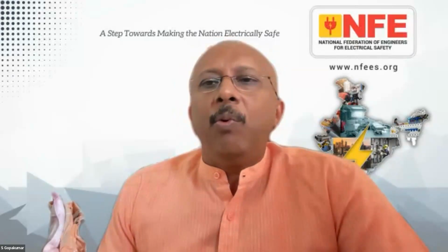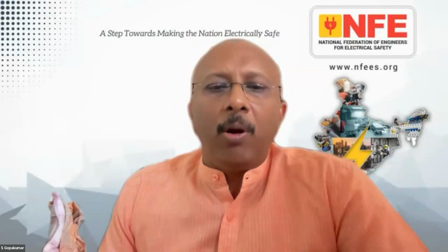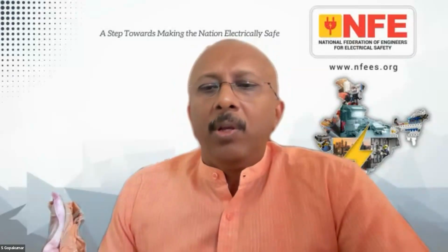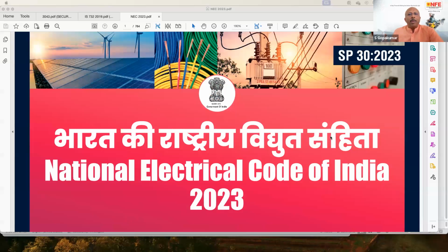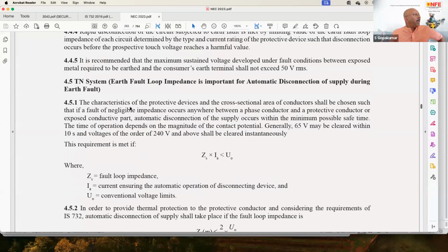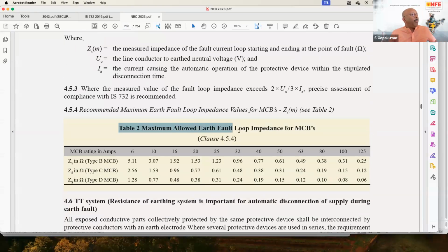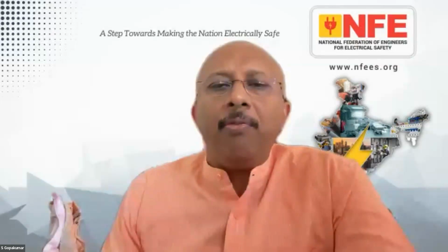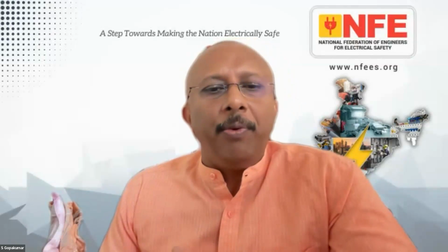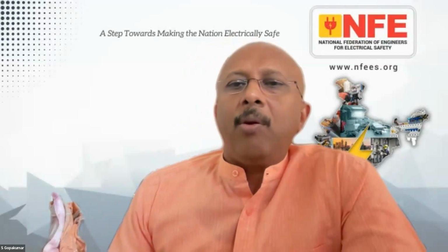You can see it. But now, somebody is asking, what is the value required for fault loop impedance? I will show you where you can find this value. Very simple. I am showing you the National Electrical Code of India 2023. Go to page number 283. Here you can see TN system, fault loop impedance and automatic disconnection of supply. You see the calculations here. Table 2, maximum allowed fault loop impedance for MCBs. For example, for a type C MCB, if you have a 32 amp MCB, the impedance shall be less than 0.48 ohm. You can download the NEC free of cost. If you read Part 1, Section 18 of the NEC, you will get a lot of idea. Thank you very much.